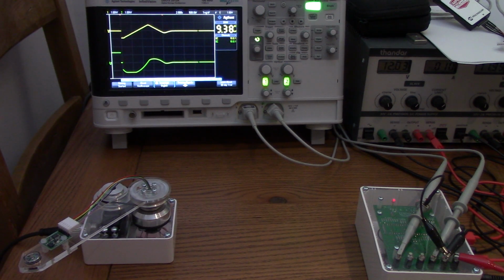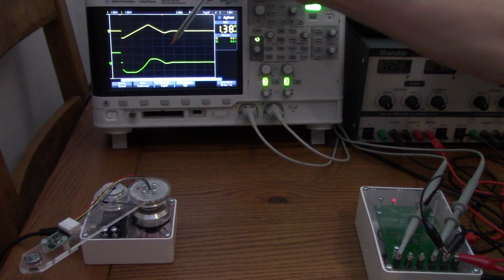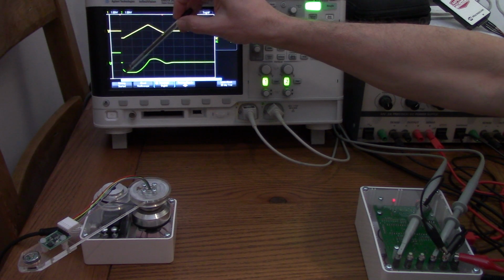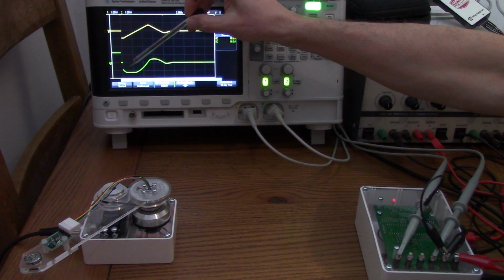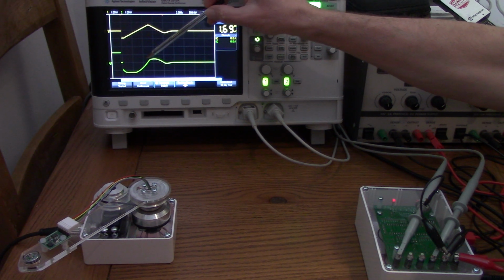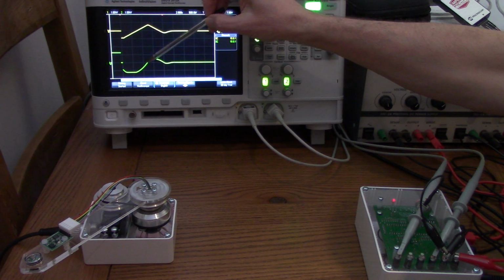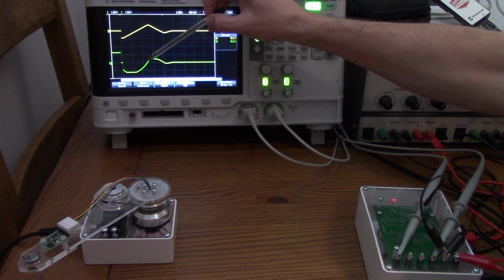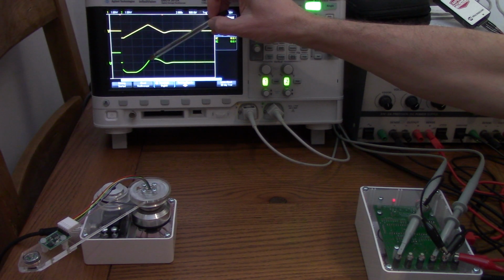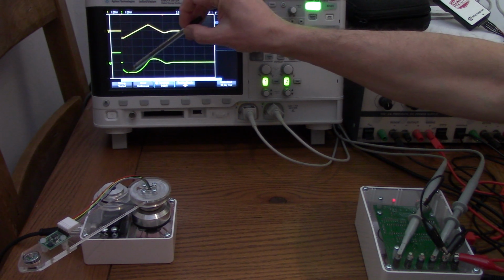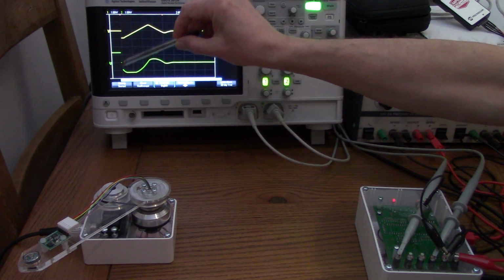Right, okay. And what you'll see here is flatlining, which is great to see. This is the summation of the proportional component and the integration component, which has been modified by the constant Ku over Tu. You'll see a flat line here, and that shows that this has actually saturated the converter.